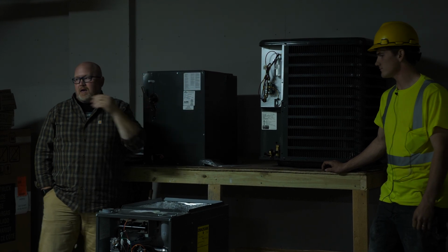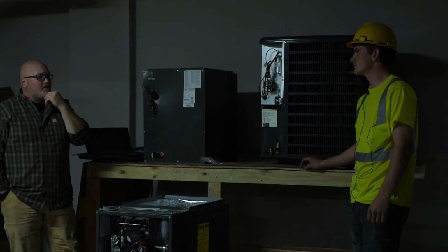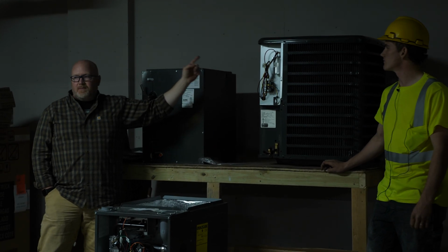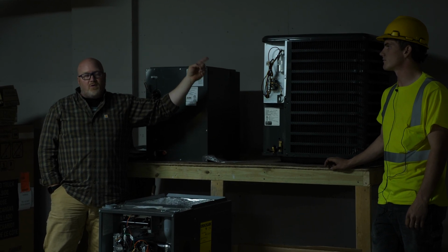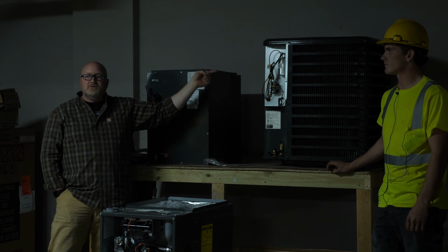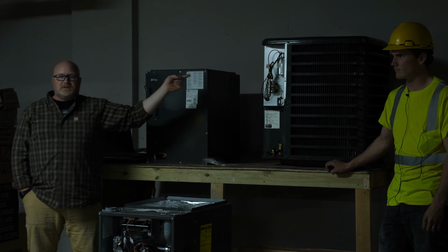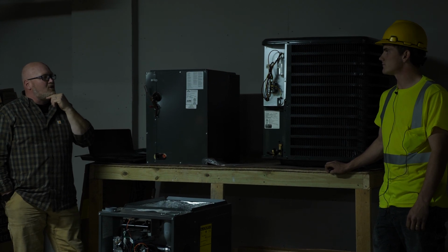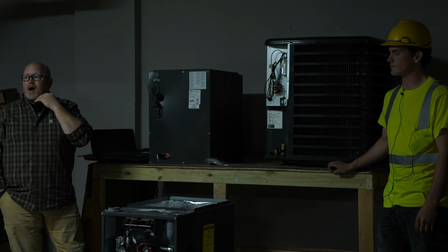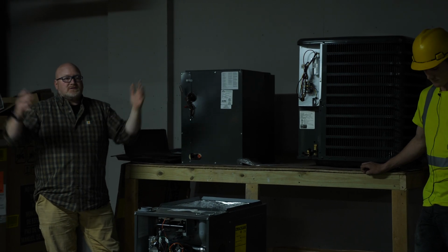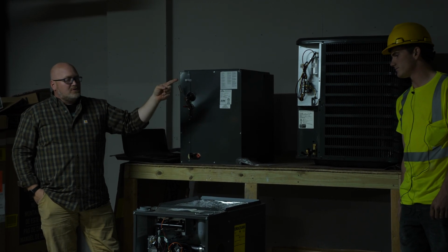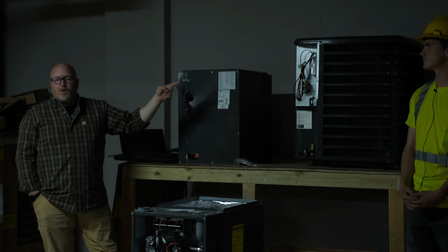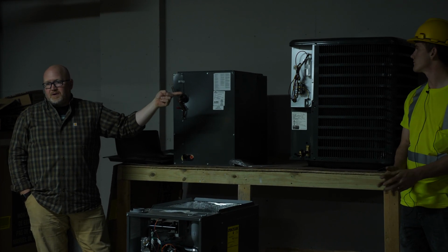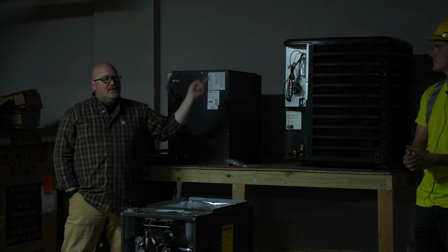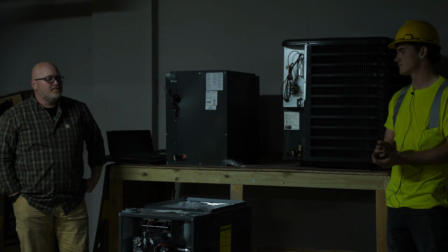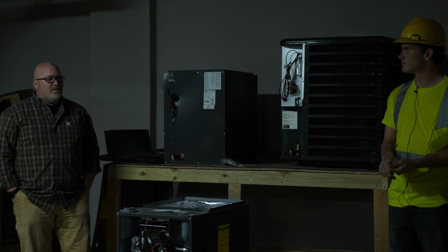Warm air, correct. And in the situation that we're doing here at Lexington Lofts, we're actually taking that waste heat energy and recovering it in a secondary heat exchanger, and we're going to use it to do pool heating. So a system that we've designed and put together will produce about 71,000 BTUs per hour that generally just gets lost. And in this situation, we have 2 compressor condensers in the garage. So instead of overheating the garage, it's a perfect application to take that waste heat energy and dump it into the pool.